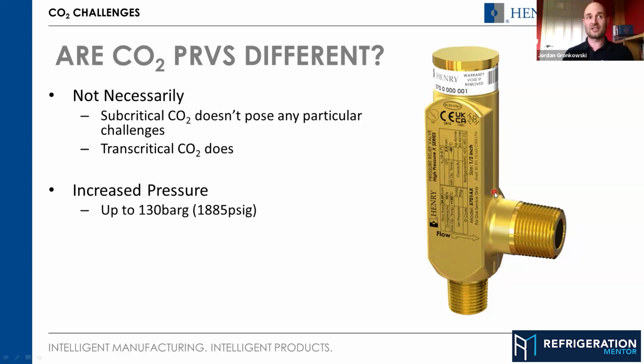The obvious one's increased pressure. I've put here 130 bar because again, that's where our limit is on our pressure relief valve range, but I've heard up to 150, 160 bar in some systems, which again has the impact as a valve designer. You have to look at the rigidity and the structural integrity of the valve at those pressures.